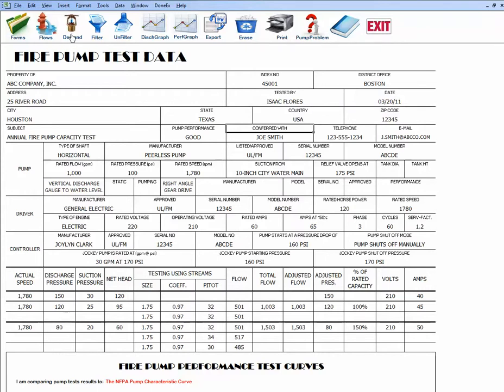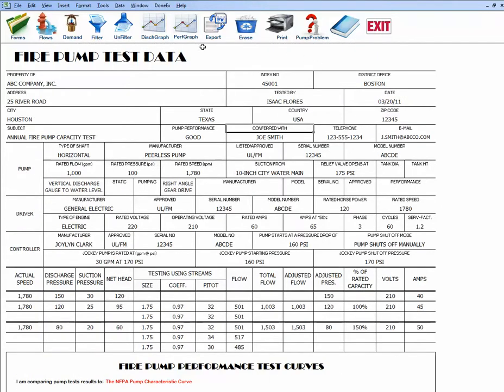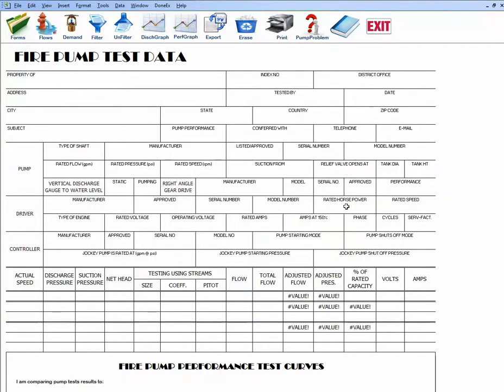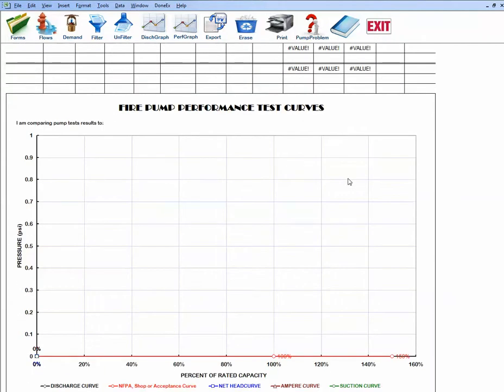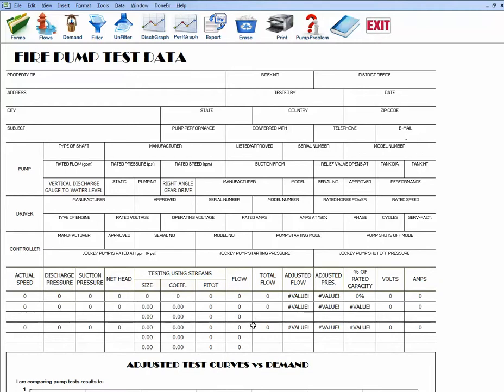To demonstrate entering test results, first clear the data by clicking Erase and confirming Yes. The form is now blank and both the discharge and performance graphs are cleared to zero. We will now start entering essential information to plot a fire pump test curve, rather than entering all previous information.